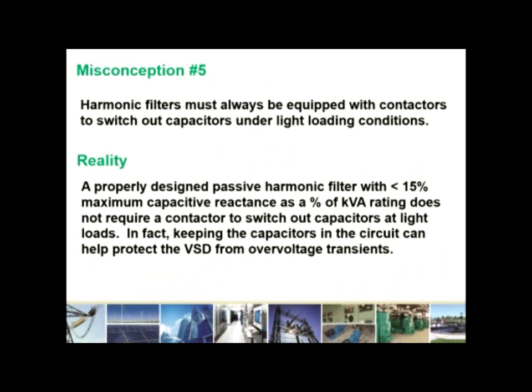So misconception number 5 is that harmonic filters must always be equipped with contactors to switch out capacitors under light loading conditions. Whereas in reality, a properly designed passive harmonic filter with less than 15% maximum capacitive reactance as a percent of kVA rating does not require a contactor to switch out capacitors at light loads. In fact, keeping the capacitors in the circuit can help protect the VSD from overvoltage transients.